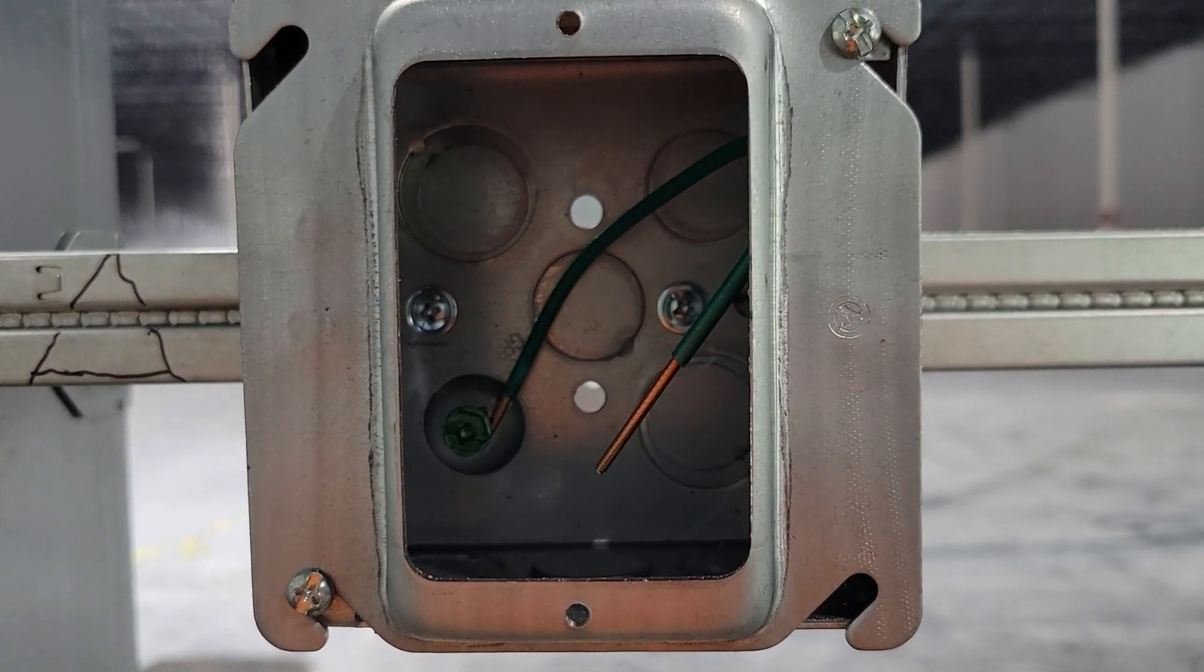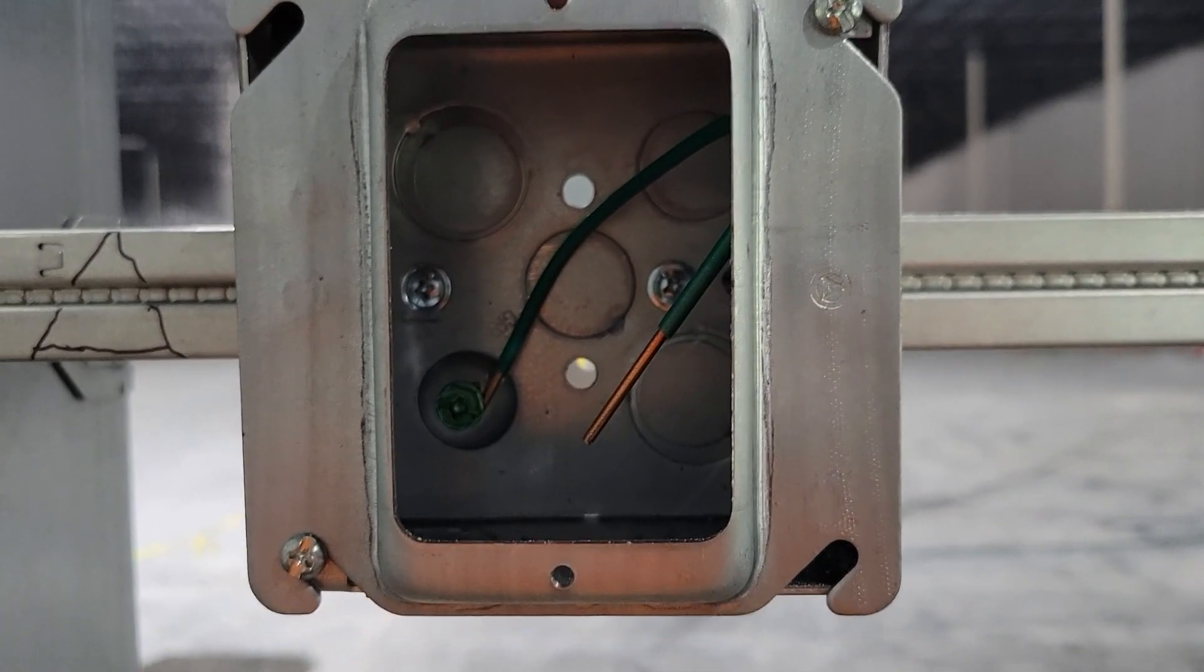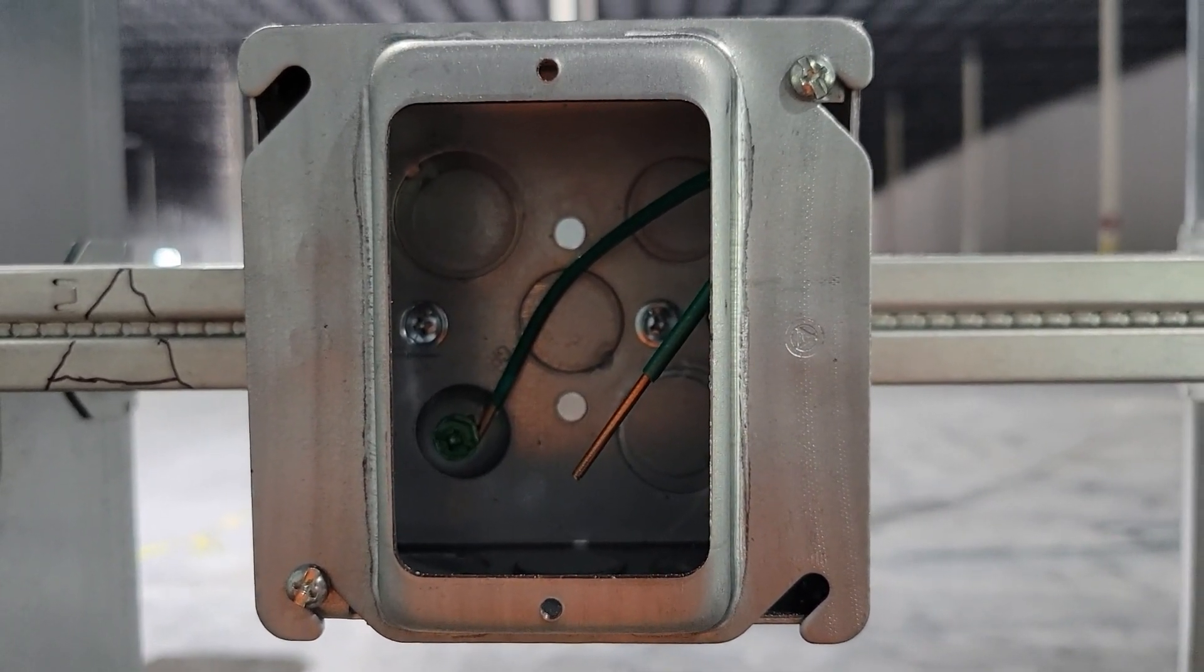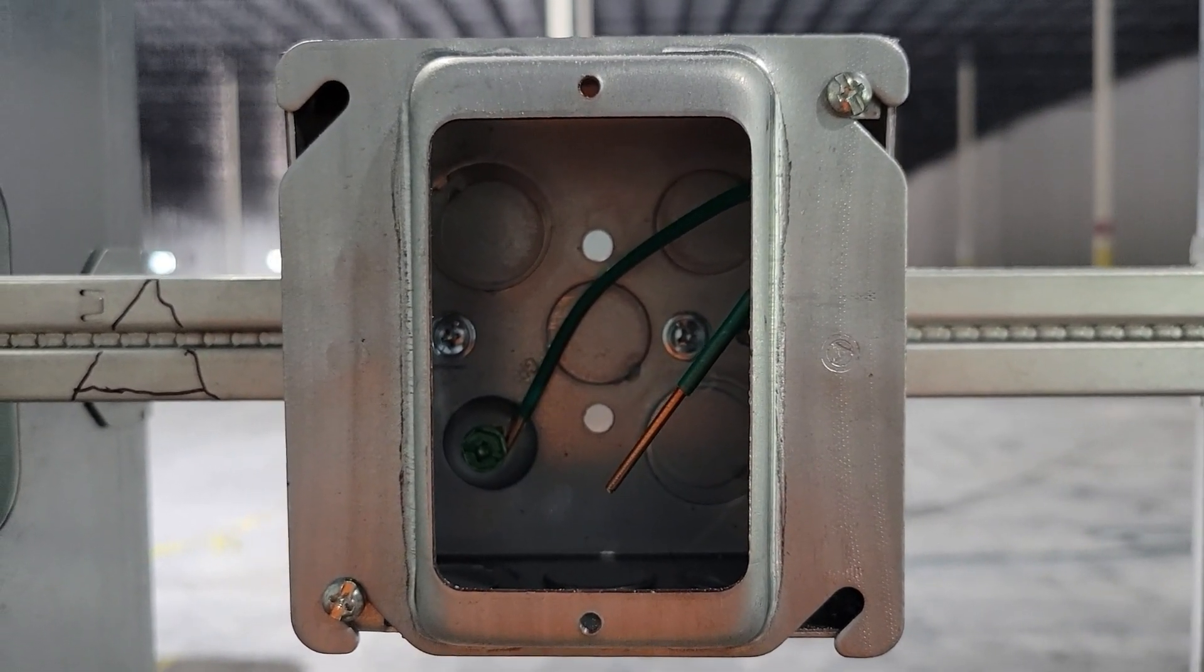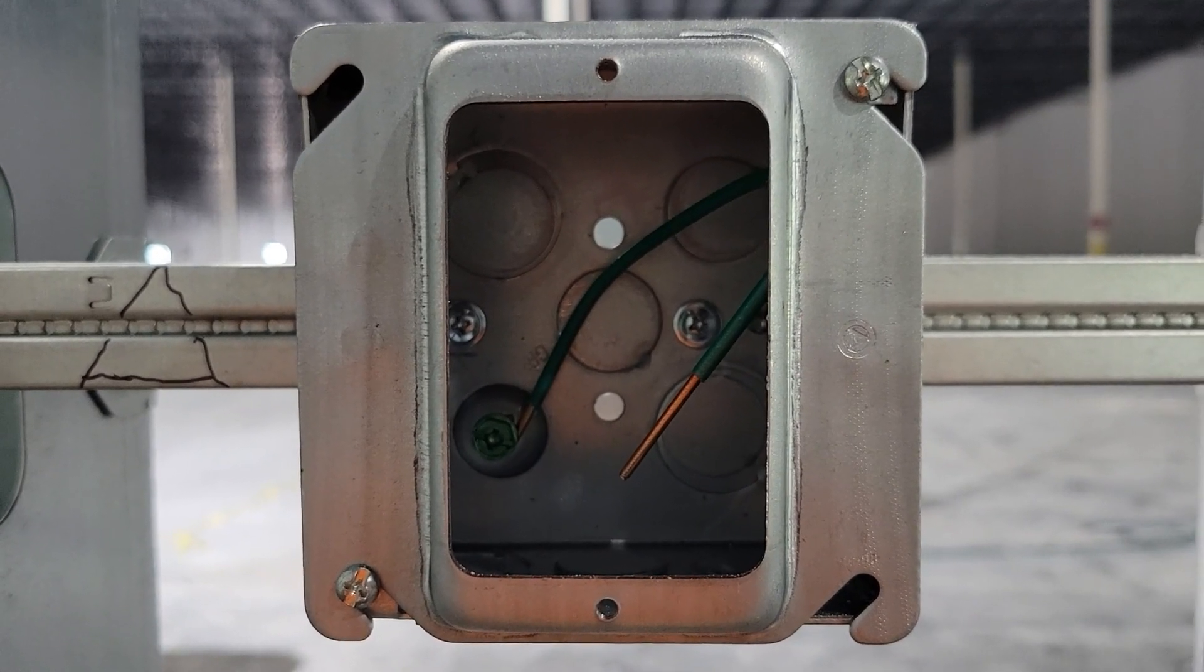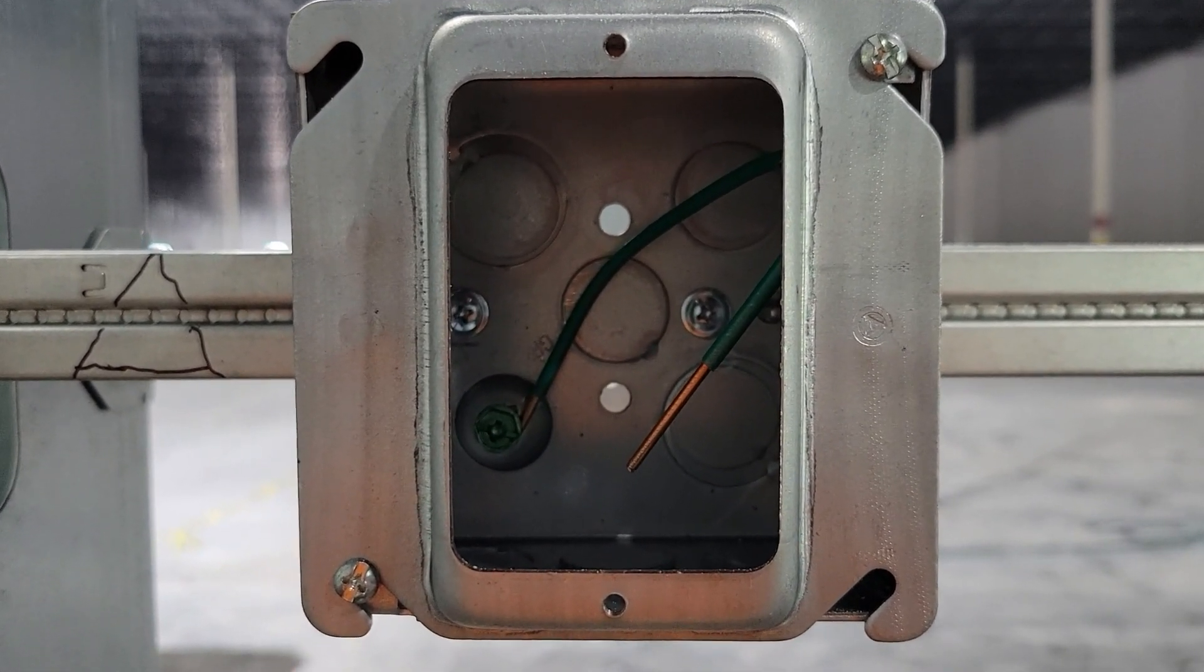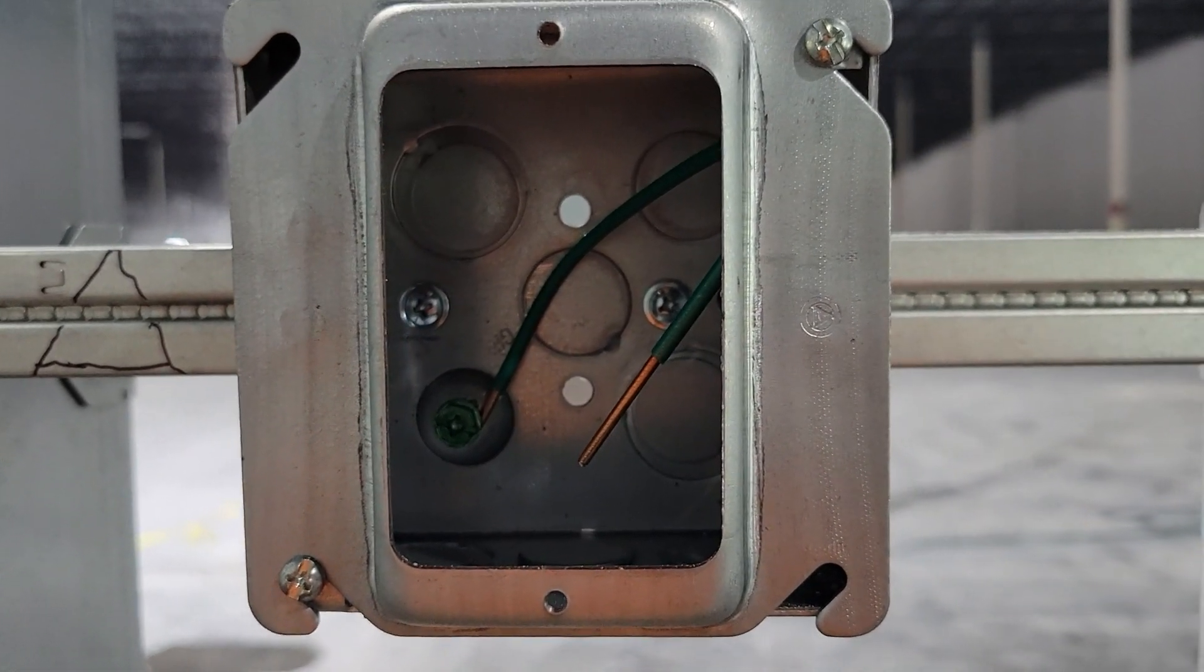Like I say, there is a couple exemptions, but you're going to have to install grounding connectors at each end of your conduit. And the green wire inside the conduit would not be pulled. It would not exist. So if you have a green wire in your conduit, use a pigtail.